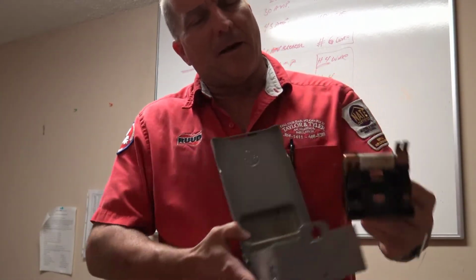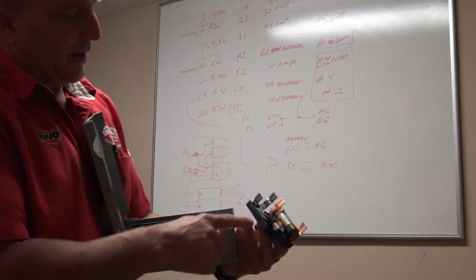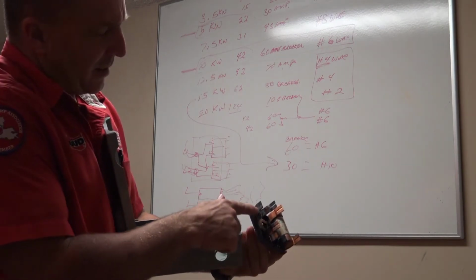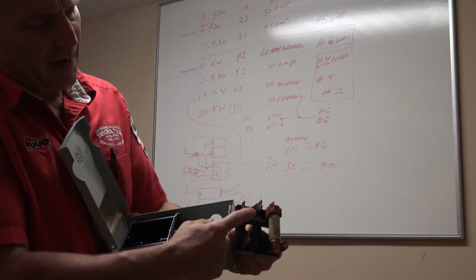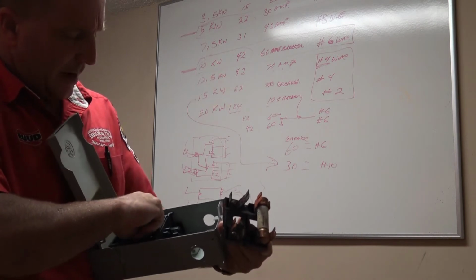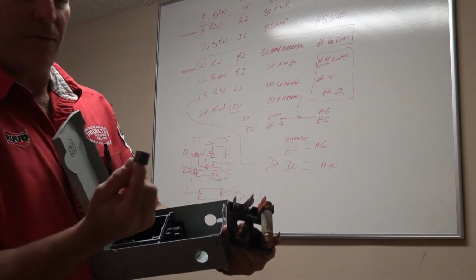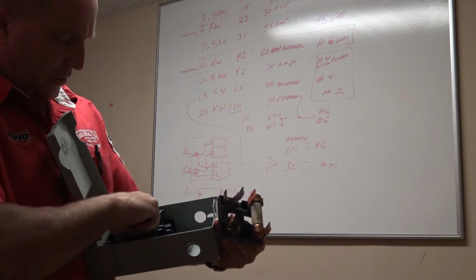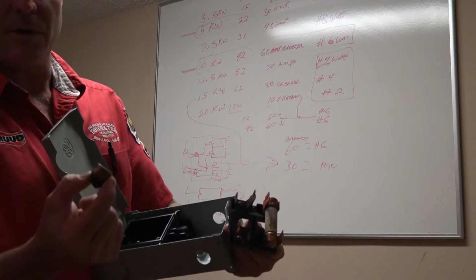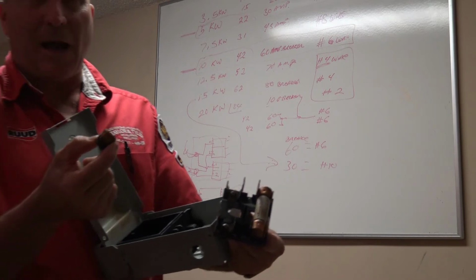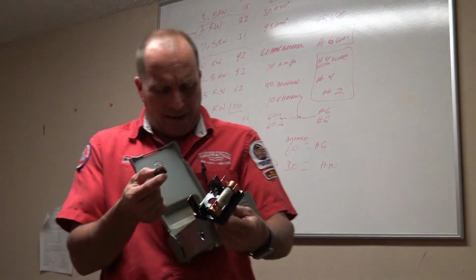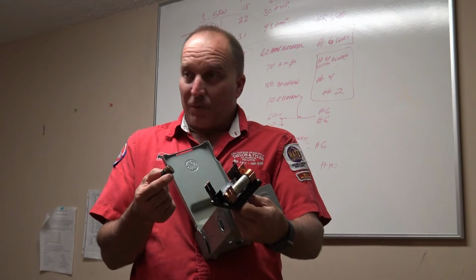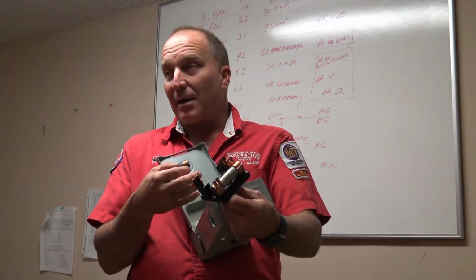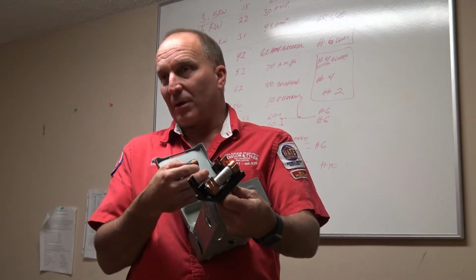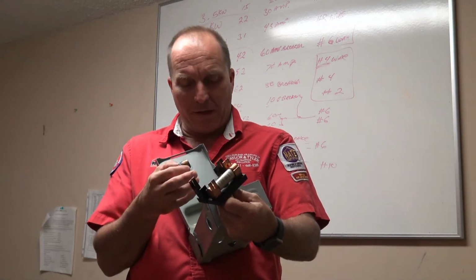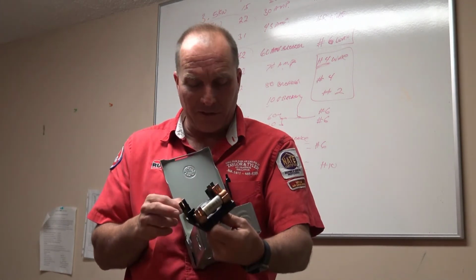When I look at this here, I can also see from the side of it, you can probably see this, it's discolored on here and it's burnt up inside of here, okay? This happens to be a piece of my fuse that was up inside of here, which is all burned up and in pieces, okay? So obviously this system did not run. With that being said, I would bet you a dime to a dollar this is probably not off a disconnect box for a condenser, but probably an electric heat system. I'm saying probably, okay? Could be either one, because it happens on both of them, obviously.